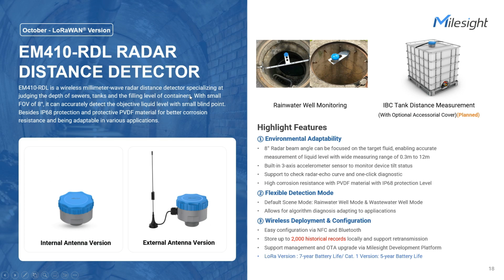The LoRaWAN-based millimeter wave radar distance detector EM410-RDL sets new benchmarks for speed and accuracy in sewer applications. Starting with installation in record time, default scene mode options, fast parameter setting using Bluetooth, and screw thread design enable a simple and customized out-of-the-box startup. This non-contact radar level measurement delivers highly accurate measurements up to 12 meters. Let's explore the functions of this excellent model. Number 1, best possible performance. The 60 GHz technology and 8-degree small detection angle enable focused and precise level measurement even in confined spaces.